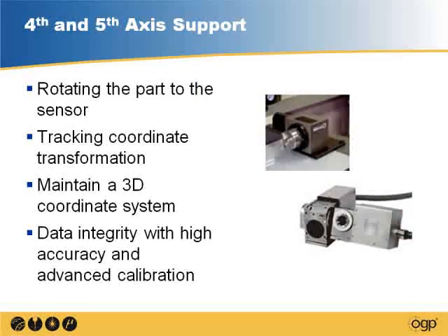Relative to fourth and fifth axis support, sometimes a sensor is rotated to the part, so an articulating touch probe is something that you might know about, and that is rotating the sensor to the part. With a multi-sensing system, since some of these sensors you can't necessarily rotate, like a laser or the video, although there are techniques for doing that, you may want to rotate the part in the fourth or the fifth axis to present the particular feature that you're measuring to the sensor in the most appropriate way. So the software has to have that integrity and be able to calibrate those axes out so that you're maintaining the micron level of accuracy.